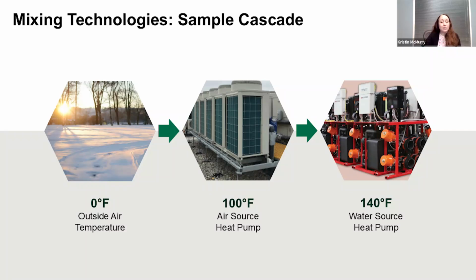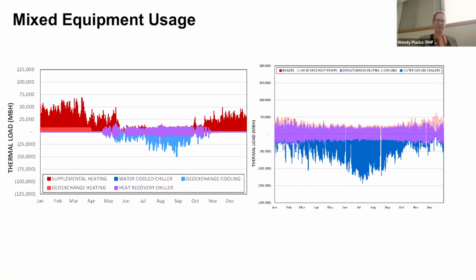Or alternatively, instead of cascading, maybe what you need to do is look at what kind of usage your campus has. You might want to use your geo-exchange heating only during a certain season of the year and maximize that as much as possible, to decrease the heating demand that would otherwise go to condensing boilers or electric boilers. You don't want to increase your electric demand, but then you want to use your heat recovery chiller. Alternatively, you could choose not to use the heat recovery chiller at all, store all the heat from your cooling system, and increase what comes out of your geo-exchange even more.